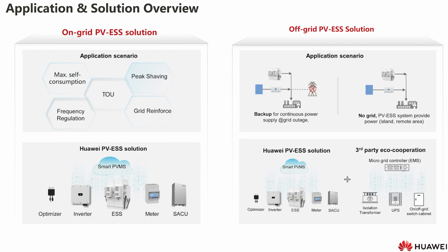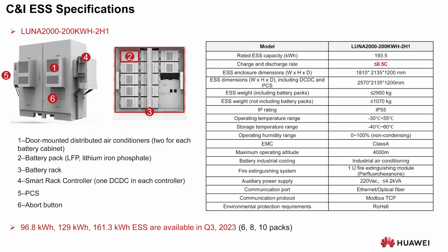When we're talking about off-grid, which is our on-off grid scenario, the application scenario will be for backup purposes only, or for a microgrid where there's no grid at all. Here you would need all of the items from the beginning, plus some third-party eco-cooperation. So you'd need a microgrid controller, an isolation transformer, a UPS, and an on-off grid switching cabinet. We'll go into more details later.